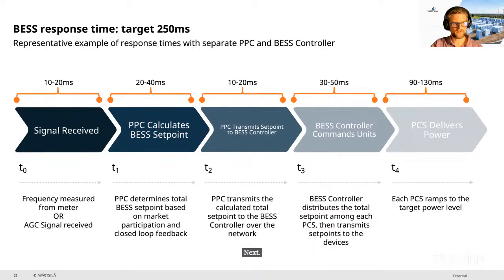Next, at T1, the PPC processes the signal, adds power from any other markets that it's participating in, that stacked operation, and adjusts based on the closed loop control feedback. At T2, the total calculated set point is then sent to the BESS controller over the local network based on some interface agreed upon by the two controls vendors, the PPC vendor and the BESS controller vendor. At T3, that BESS controller receives its target from the PPC, processes the signal, applies its algorithm to distribute the power across the units, and then transmits a set point to each PCS in each of those units. And then finally, at T4, each PCS begins to respond and ramps up to the target power level.